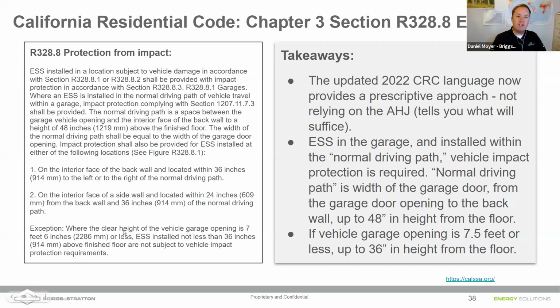Where the clear height of the garage opening is 7 feet 6 inches or less, and the ESS is 36 inches above the finished floor, you don't have to put in bollards. That's great, but keep in mind that 36 inches off the floor might result in a battery being quite high up. For our batteries that are 5 feet tall, this is probably not possible.